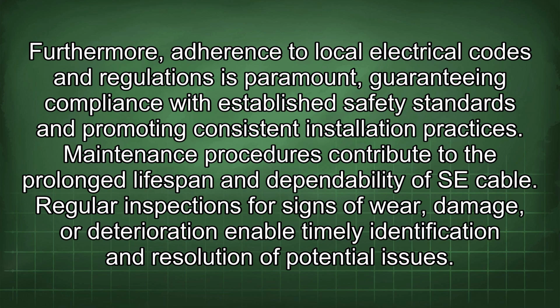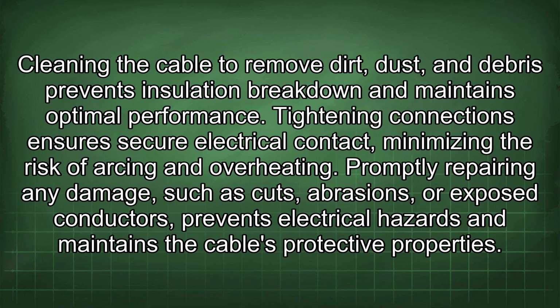practices. Maintenance procedures contribute to the prolonged lifespan and dependability of SE cable. Regular inspections for signs of wear, damage, or deterioration enable timely identification and resolution of potential issues. Cleaning the cable to remove dirt, dust, and debris prevents insulation breakdown and maintains optimal performance. Tightening connections ensures secure electrical contact, minimizing the risk of arcing and overheating. Promptly repairing any damage, such as cuts, abrasions, or exposed conductors, prevents electrical hazards and maintains the cable's protective properties.